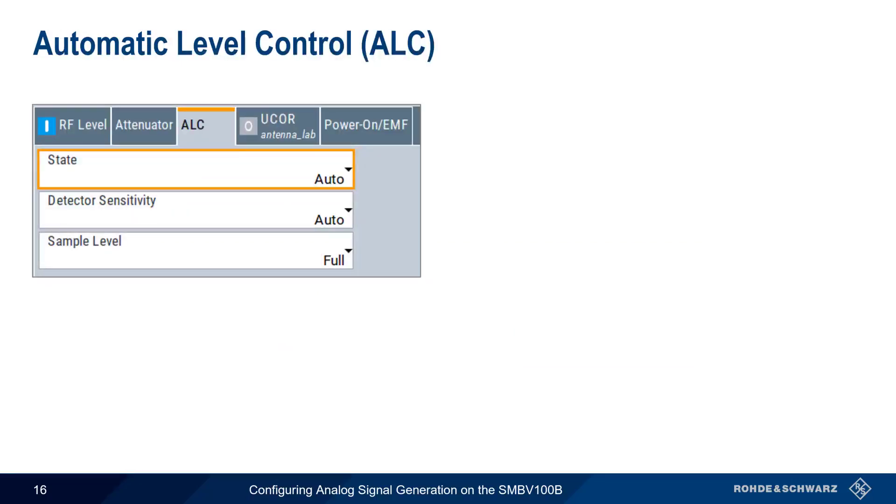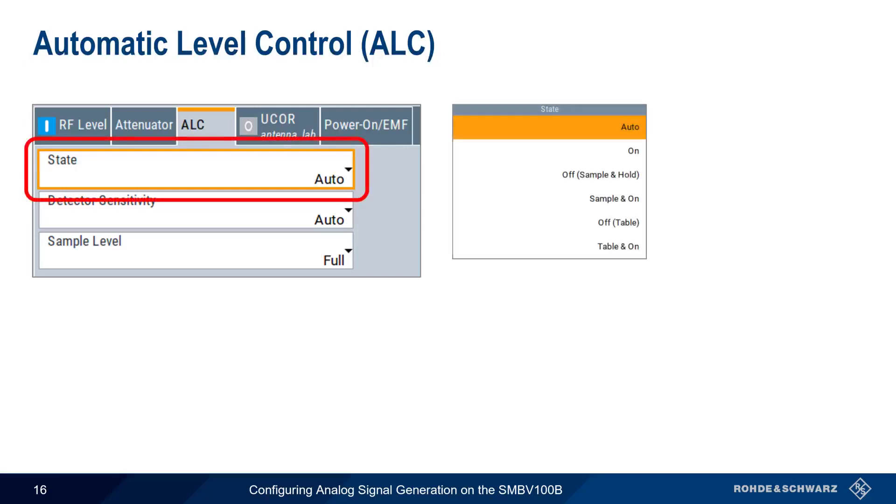Another way of optimizing level accuracy on the SMBV100B is through automatic level control, or ALC. ALC is an adaptive control system to stabilize the RF output level. It continuously monitors the current level and adjusts it to keep a steady state over temperature and time. ALC is active in almost all applications by default, but the level control can be implemented in different ways depending on the setting for State. As the name implies, Auto selects the most appropriate ALC mode automatically, while ON activates ALC permanently. The ON setting provides the highest level accuracy and also maintains the level even when ambient conditions, such as temperature, are changing.